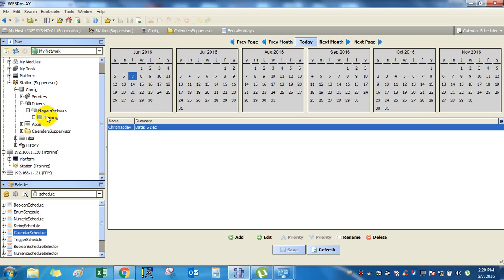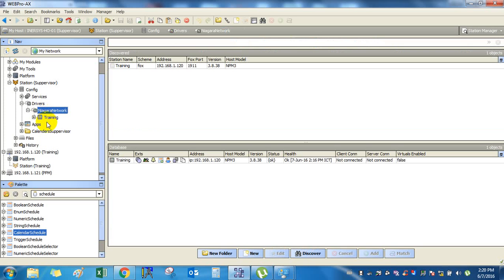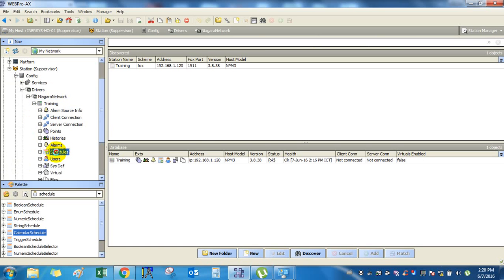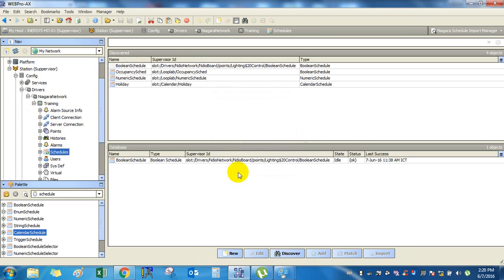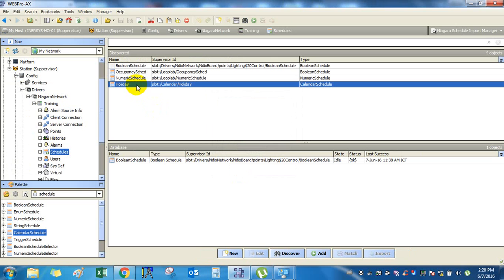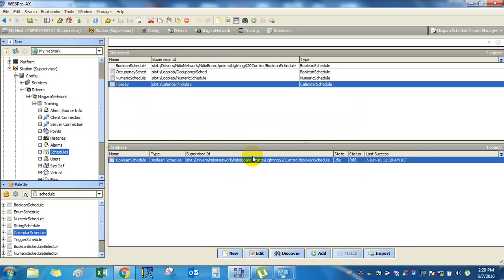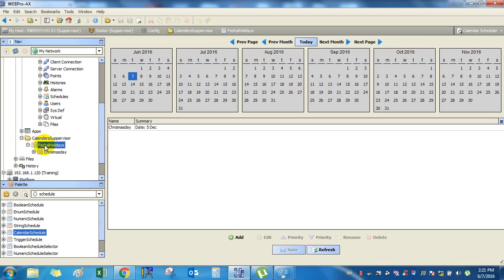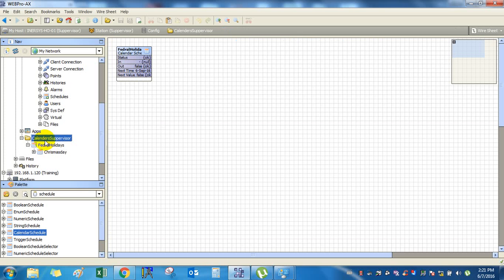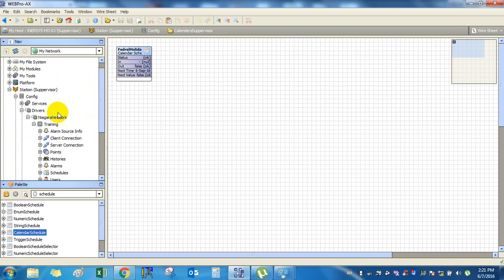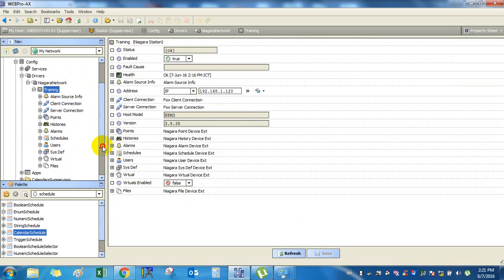Once you have the schedule imported, go to the loop lab here. Go to the numeric schedule, go to the special events. Add this event as probably the same thing, federal holidays, and it is going to be a reference. And now, instead of choosing the calendar from my local station, I'll choose it from the Niagara network which I just imported and say OK. I'll configure the same unscheduled value here. Hit save and go back.